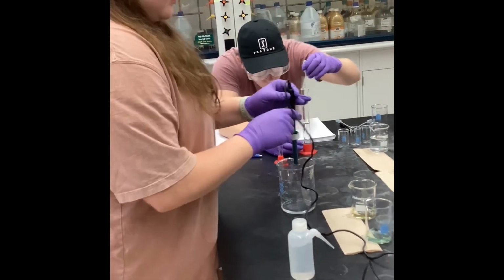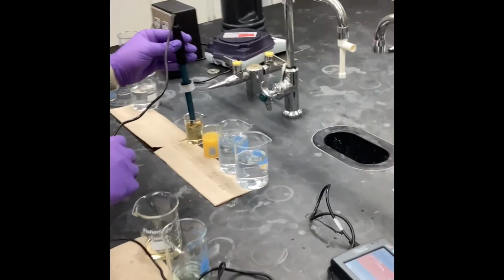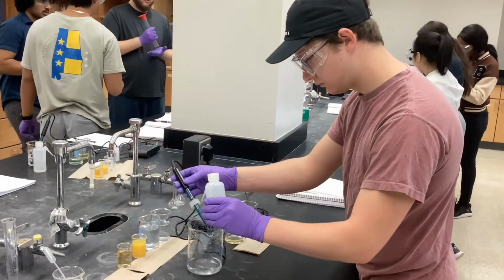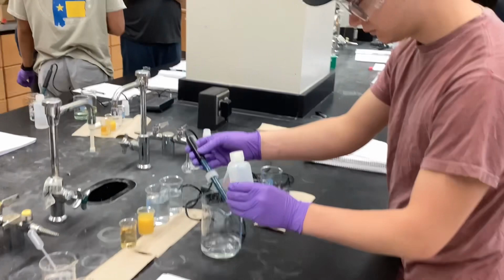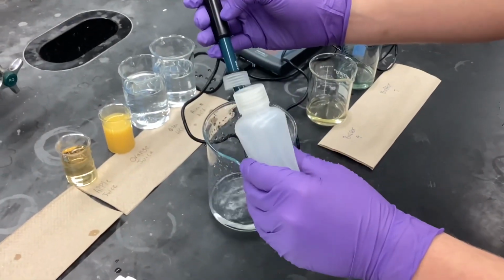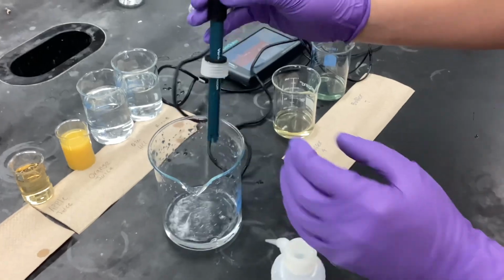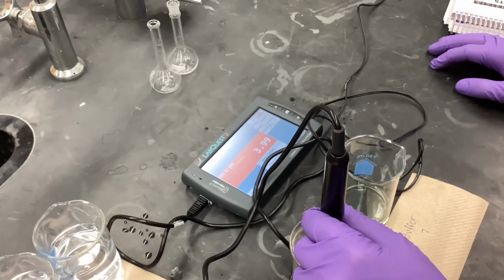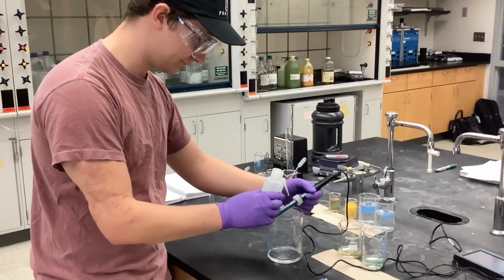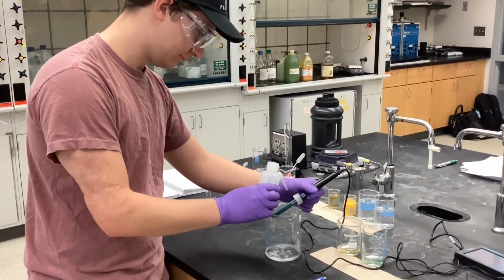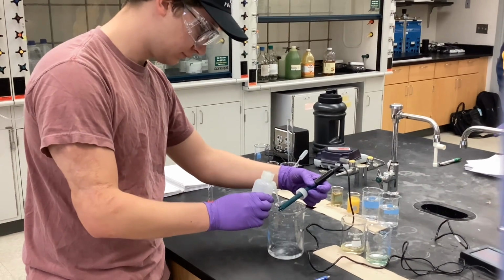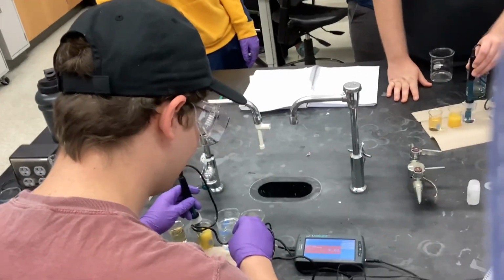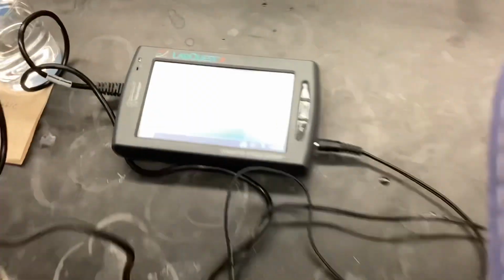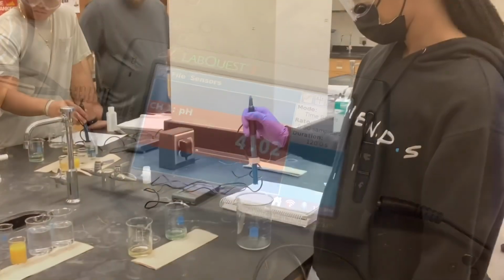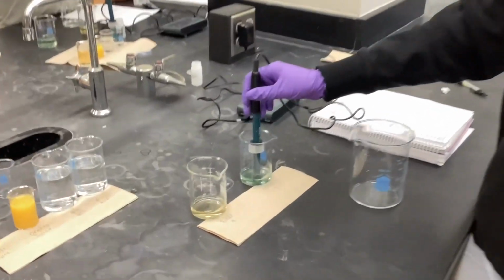Before we do any more solutions, we must clean it off. So now I am sticking it in the apple juice, and this was our pH for our apple juice. I'm cleaning off the pH meter to test the buffer again to make sure our calibration is correct. Now I'm cleaning off the residual buffer from the test to test my pH of orange juice. Now I'm going to wait for the pH to stabilize. Preparing the pH meter and testing the buffers, making sure everything is still okay.